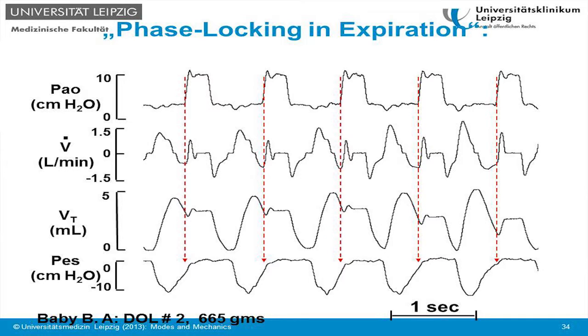The worst occurrence is phase-locking expiration. Here you can see the patient inhales, but the machine does nothing, and when the patient exhales, we get an artifact here, and the machine initiates a breath. So the machine initiates inspiration every time the patient wants to exhale, and this is like a phase shift of 180 degrees. The patient tries to inhale here and here and here, and the machine does it exactly the other way around. When the patient tries to exhale, the machine inhales.